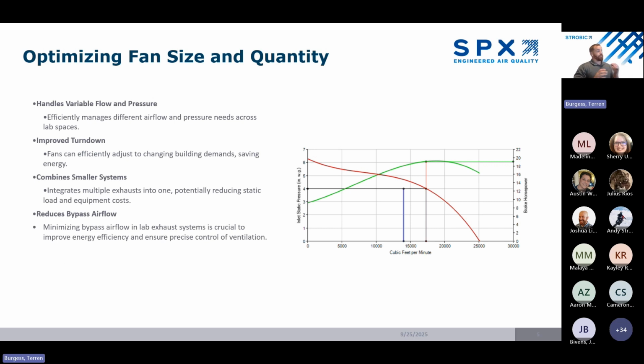So when we talk about optimizing fan size and quantity, a key feature of sustainable lab design is the ability of the system to handle variable flow and pressure. Different labs, hoods, and processes rarely demand the same airflow at the same time. And by designing systems that can efficiently manage these fluctuations, we can maintain safety, all while avoiding wasted energy. And this is going to tie directly into turn down capability, right? So with the right fan technology, the right size design, we can scale airflow up and down as the building demand changes. And that flexibility is absolutely critical, right?